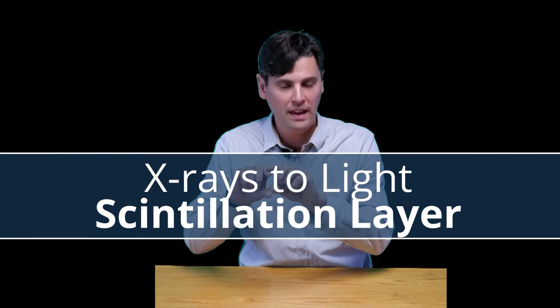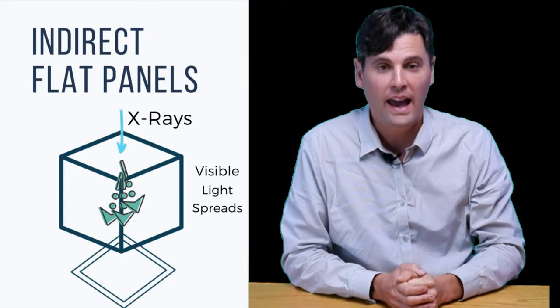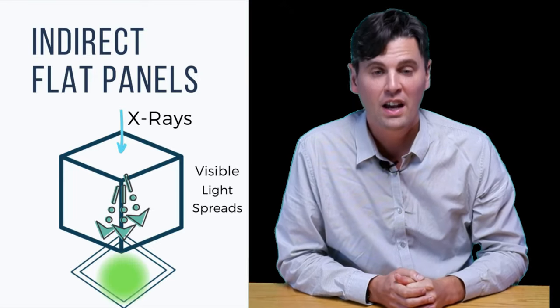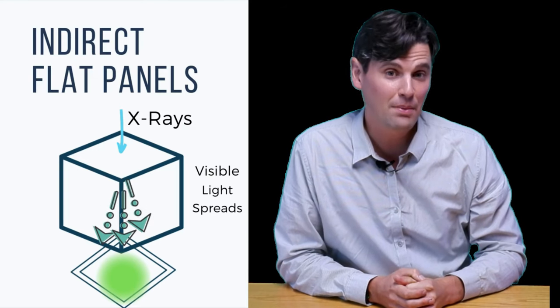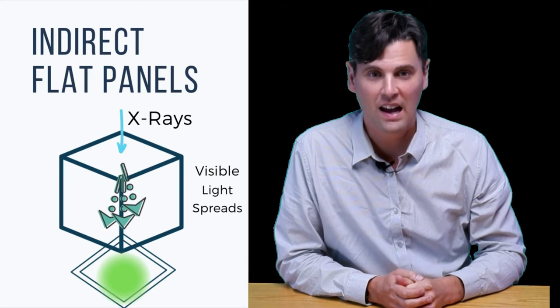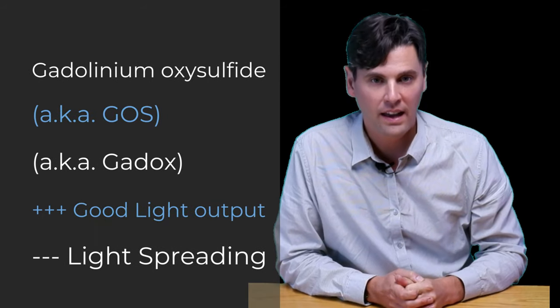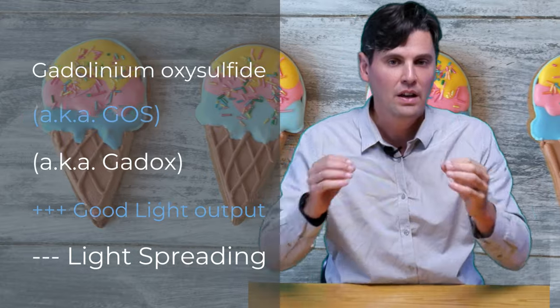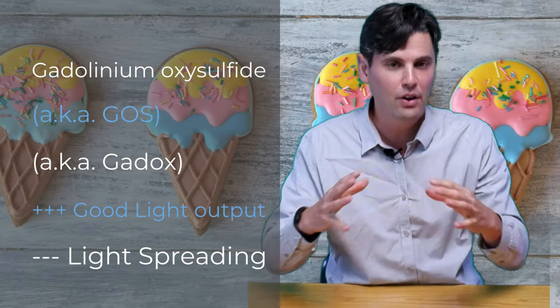Both types of indirect flat panels start with one thing: a scintillation layer. That's the layer in which the x-rays come down and interact. Out from that interaction comes visible light. One scintillator option is gadolinium-based, often referred to as GOS or gadox. The gadolinium-based scintillator has good light output, but the light comes out relatively isotropically in a cone from where the x-ray interacts.